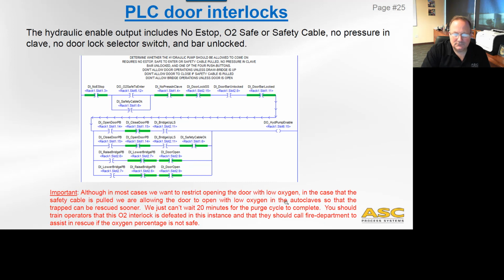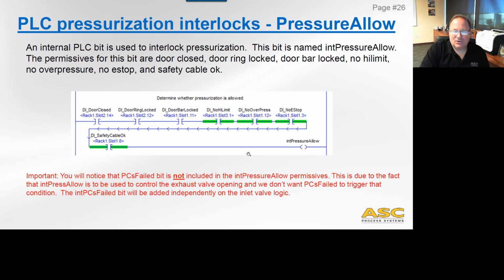So that's the case. Now you might say, so here's another point that we already made, but although in most cases we want to restrict door opening, in the case that the safety cable is pulled, we are allowing the door to open with low oxygen in the autoclave so that we can rescue that trapped person. We can't wait 20 minutes for a purge cycle to complete, right? Because at that point the guy's going to be dead. So this is again something that you want to train operators about and let them know about this specific operation, that the door can be opened in an unsafe oxygen condition when there's a safety cable incident.